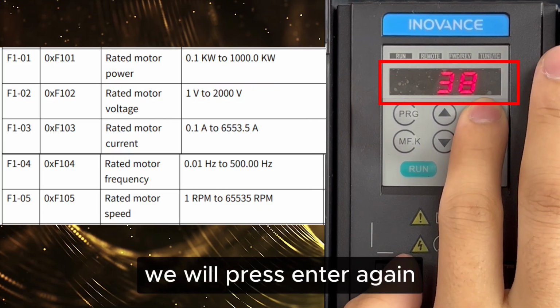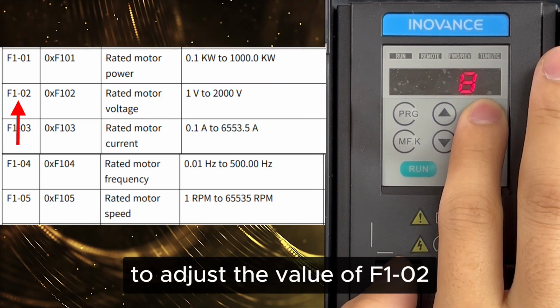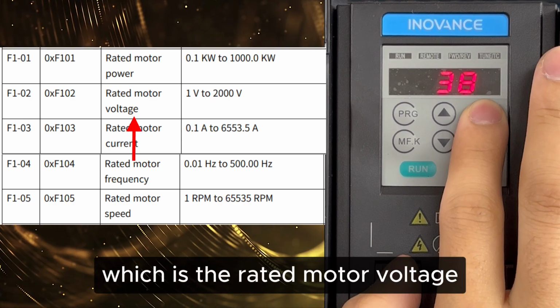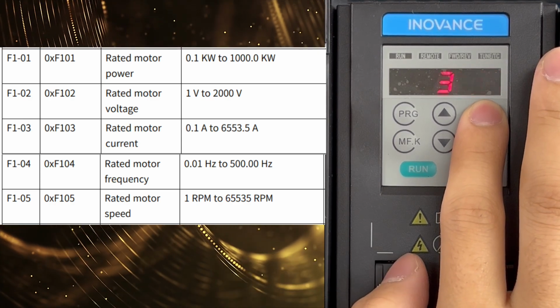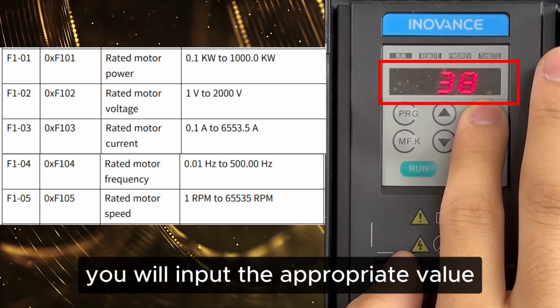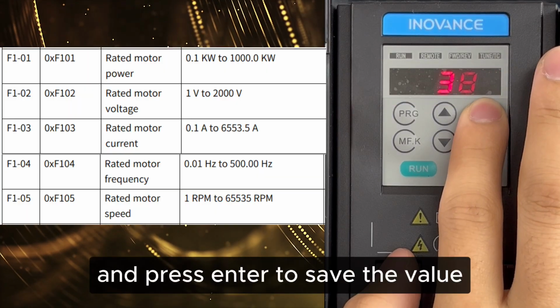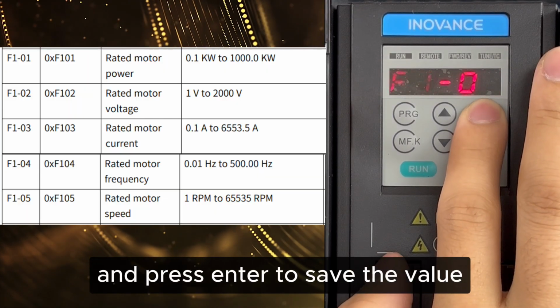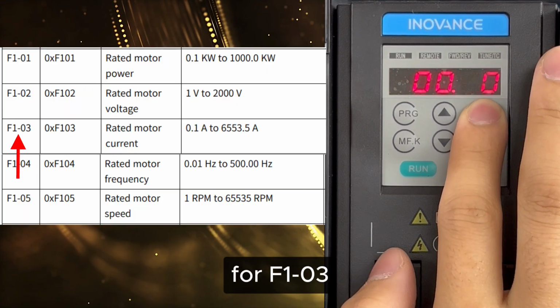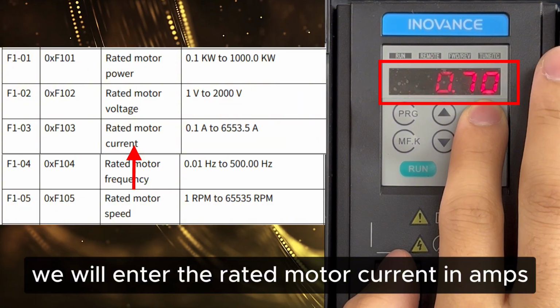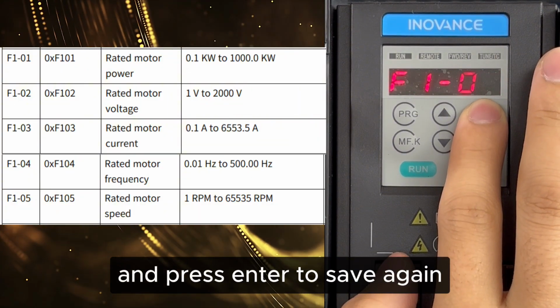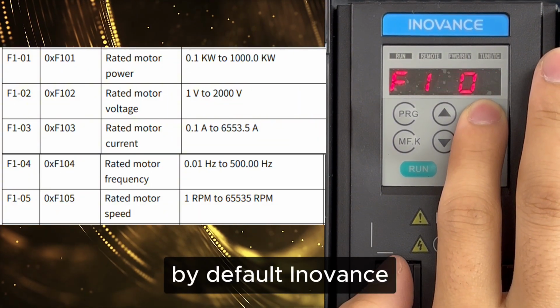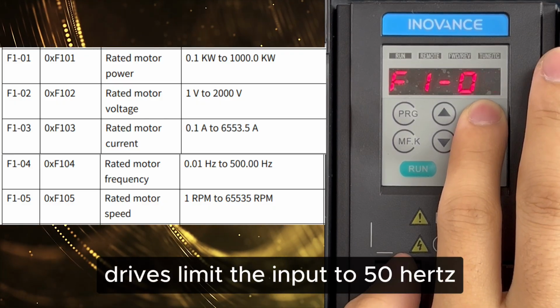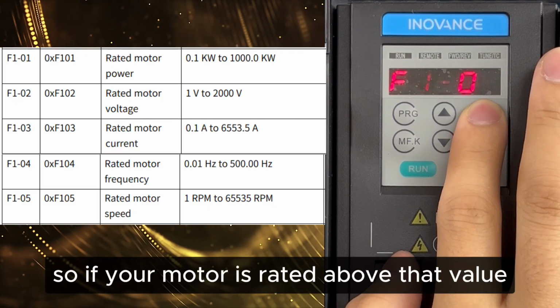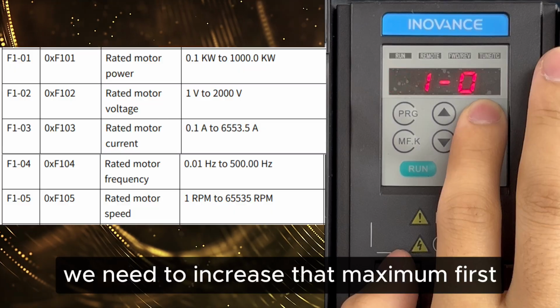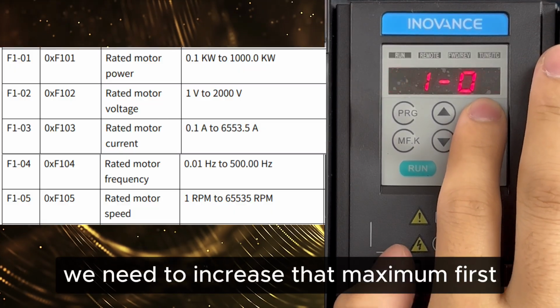We will press Enter again to adjust the value of F1-02, which is the rated motor voltage. Once again, you will input the appropriate value into the field and press Enter to save the value. For F1-03, we will enter the rated motor current in amps and press Enter to save again. By default, Inovance drives limit the input to 50 Hz, so if your motor is rated above that value, we need to increase that maximum first.